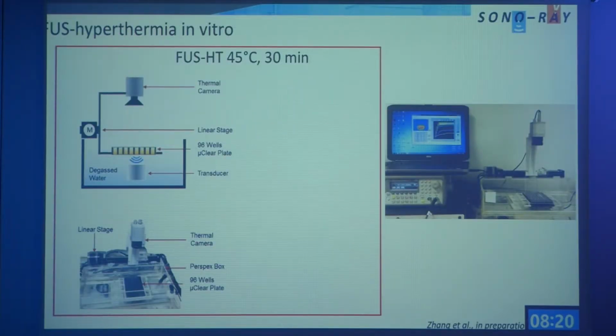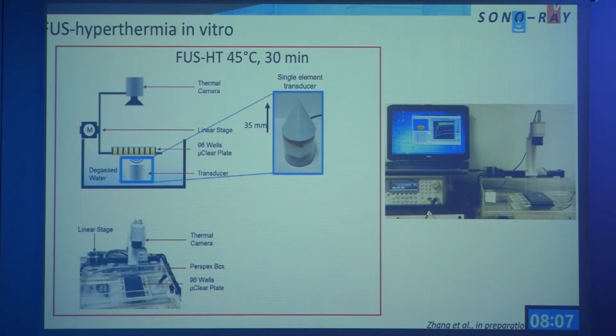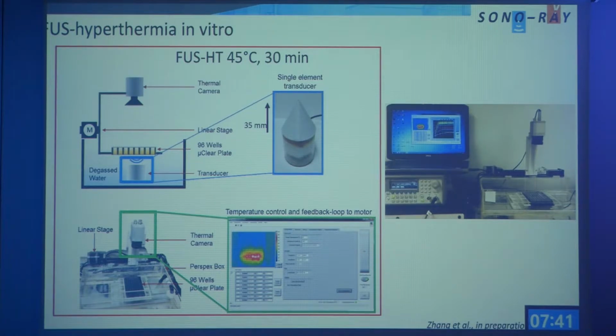So here you can see our focused ultrasound device for in vitro study. Underneath here is the 1 megahertz single focus transducer. The reason we chose a frequency of 1 megahertz is because this is the most commonly used in clinical devices. And the tumor cells are seeded in a special ultrasound-penetrable 96-well plate. The focus point is exactly positioned at the bottom of the plate, where the cells are growing. Then we use the thermal camera here to monitor the temperature changes during treatment, with a feedback loop to the motor.